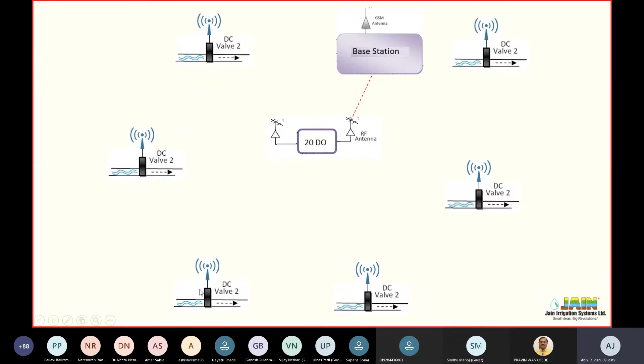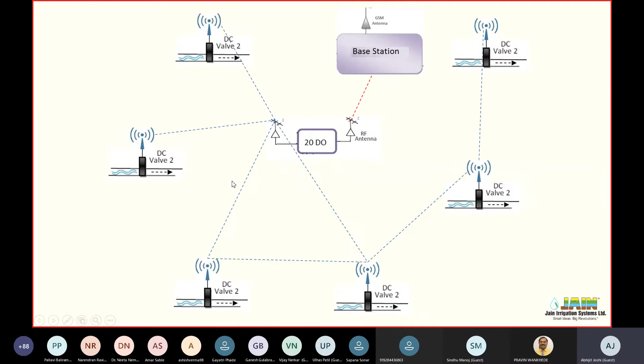So we came up with a concept. Yesterday, Sam Koshi talked about a PICO concept. A PICO concept is like from master to slave, and then the slave becomes a master for other slaves. So we came up with an intermediate RTU, which has the capacity of operating 20 valves, 20 digital outputs. There is no input, because for field valves you don't need an input. There are several small RTUs we call last mile communication RTUs. Each RTU has the capacity to operate 2 valves, so it is 2 DO, 2 digital outputs, and several such RTUs are communicating with this 20 DO, and the 20 DO in turn is communicating with the master station. So this is master and this is slave, but then this becomes master for these slaves. This is the communication methodology we also adopted in the Ramthal area.